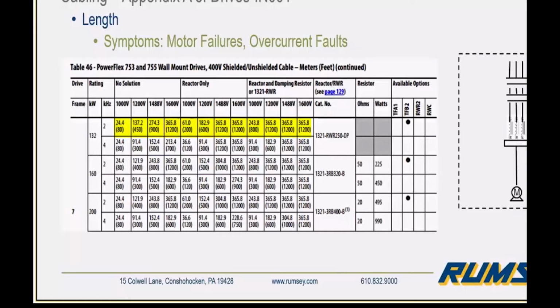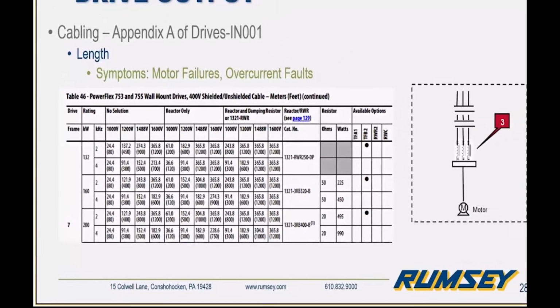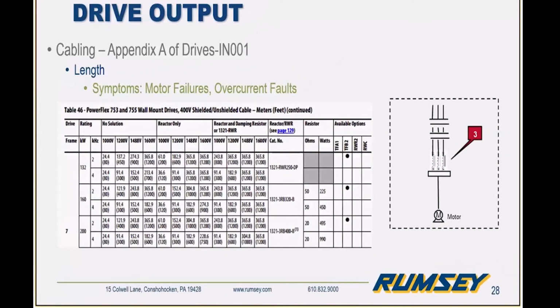All right, so based on the columns shown in this table, we can see what the resulting voltage peak is for each different lead length. So we can determine if a reactor is required for however long our distance run is to the motor, if we need to add a reactor or a dV/dt filter, for example. One additional thing to note here is that cable charging currents are not taken into account on this table.